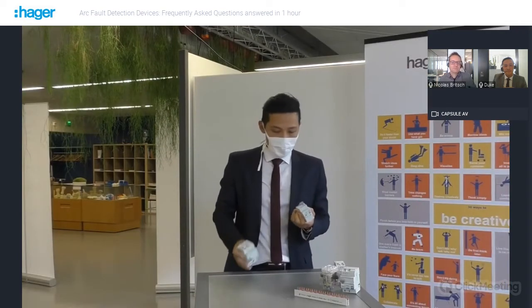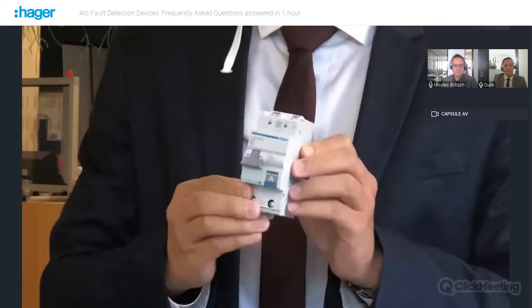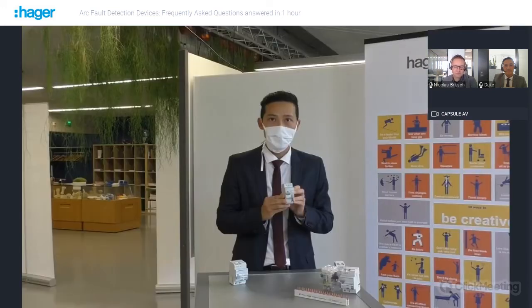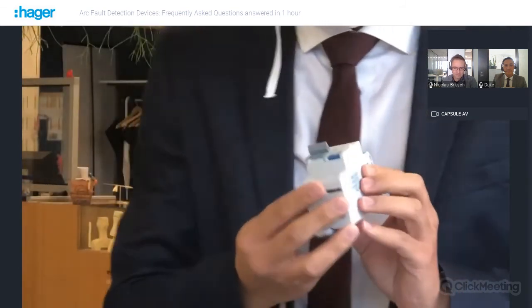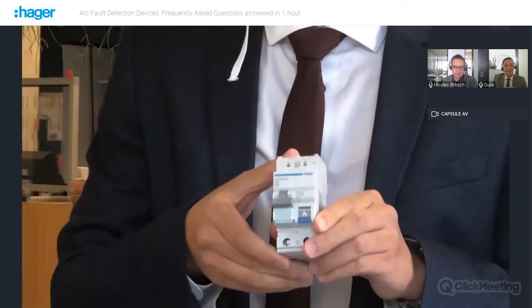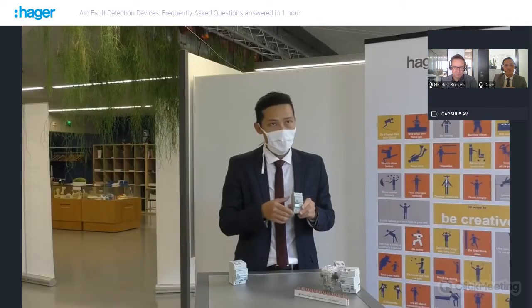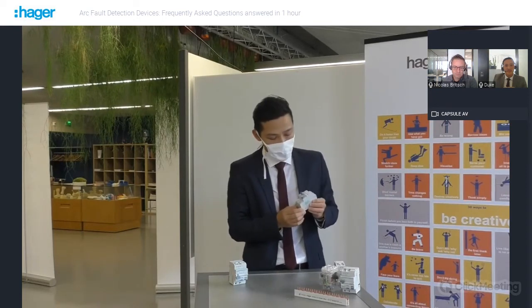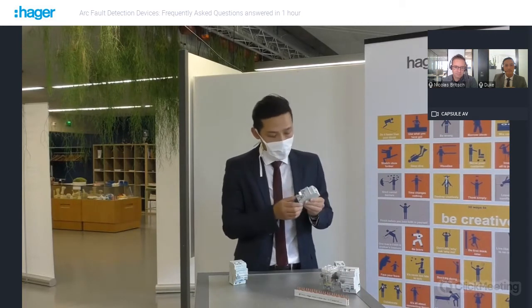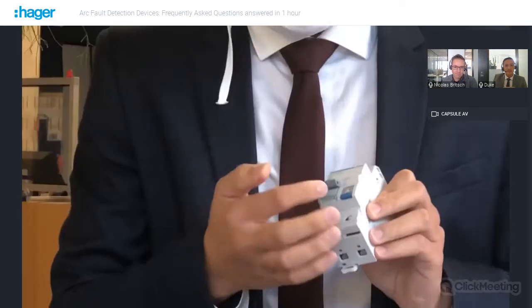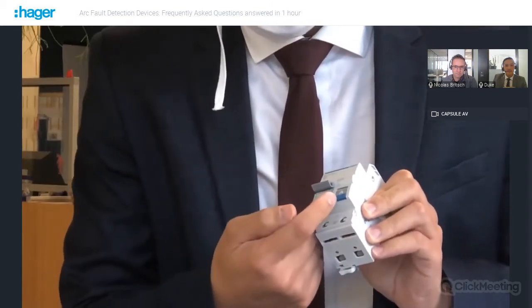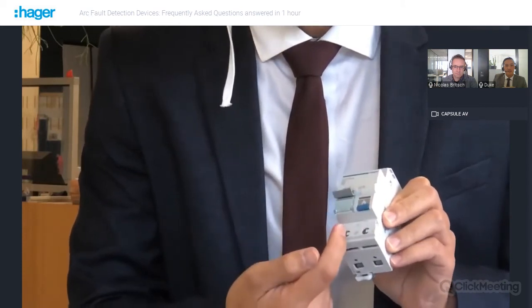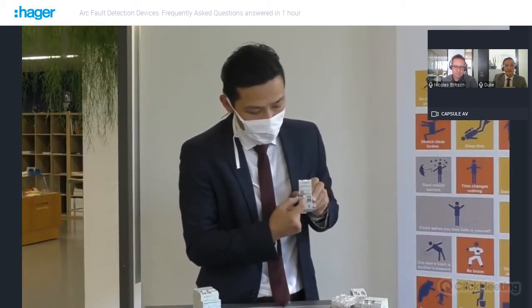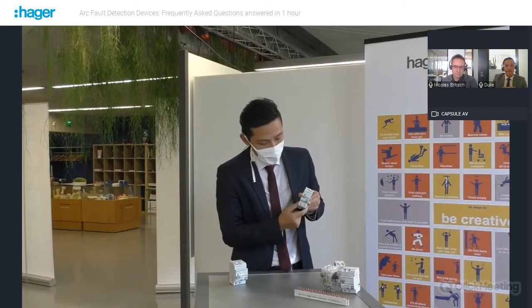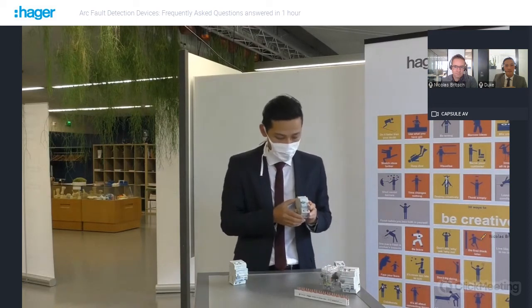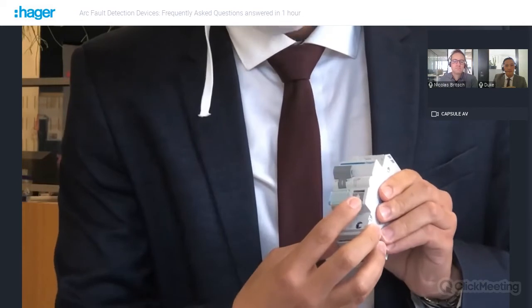Now I'm going to show you the design of the AFDD combined with MCB. This product is compliant with the IEC EN 62606 standard and of course with the MCB standard. We have a complete range with high breaking capacity, 6 kA and 10 kA. Variable tripping characteristics, curve B and C for the circuit breaker. We also have a high current rating up to 40 amps. We have different functions, for example the arc fault indicator, which helps to ease the identification between the AFD function and an MCB function. We have a handle, robust and large, in order to facilitate operations, which can connect with the other auxiliary devices. For product safety we have a test button for the arc fault detection function.